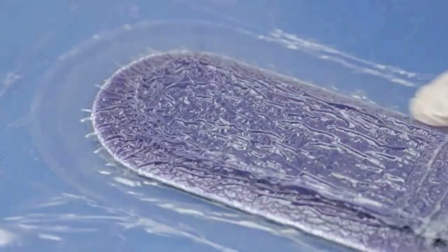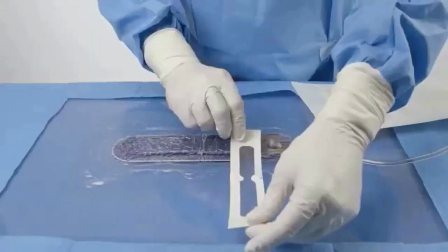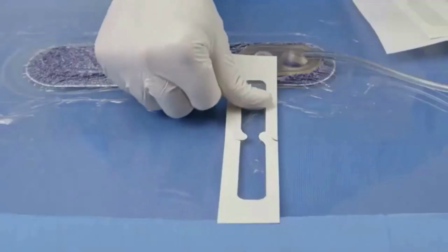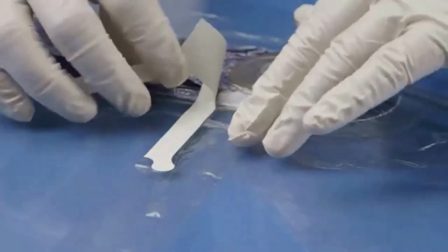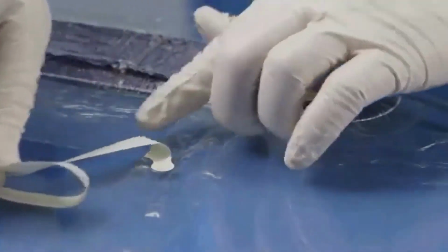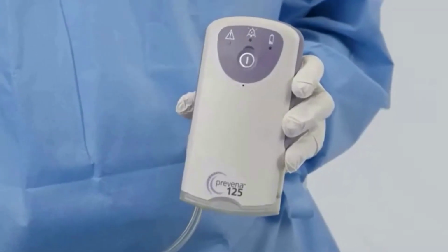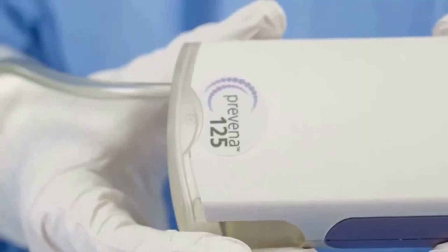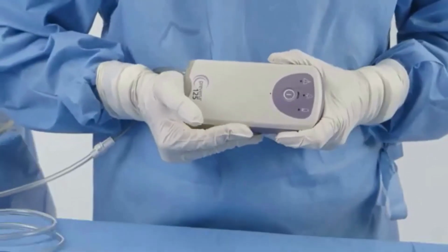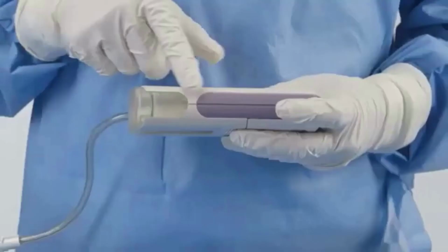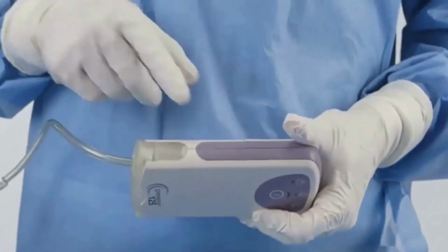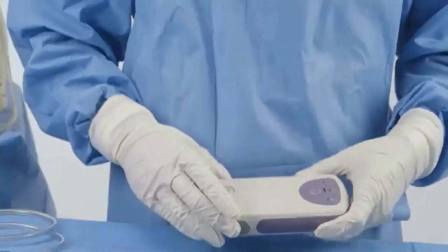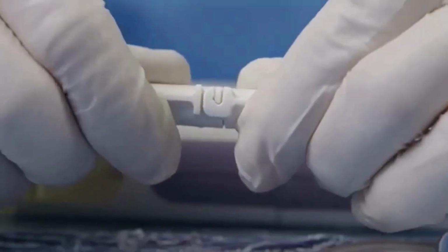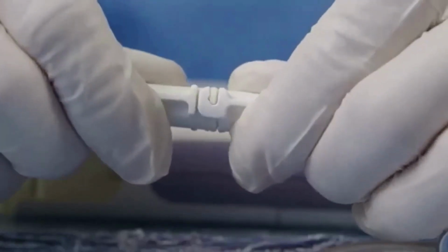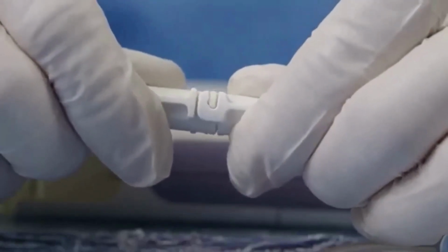Use your finger to smooth out any creases or wrinkles. 2. Use excess patch strips along the outer edge of the drape to seal any leaks. 3. Ensure that the canister is securely locked in the therapy unit. Press the canister in fully until the tabs on the canister are flush with the unit. You might hear clicks indicating the canister is fully secure now. 4. Check tubing connectors to ensure that they are fully engaged and locked.